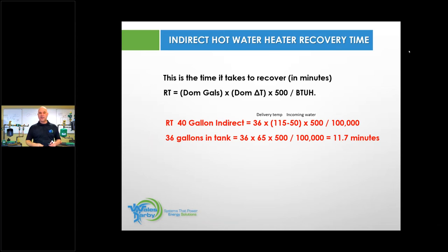I will transfer that heat energy over to that indirect. That indirect will be satisfied at 115 degrees in 11.7 minutes. And you're going to go, wow, that's a great indirect. There's no brand on there. There's no nothing. But you're going to say that's a great indirect because it heated up so quickly. Well, it heated up so quickly because you have it piped and pumped properly. All right, I'll give you another scenario.